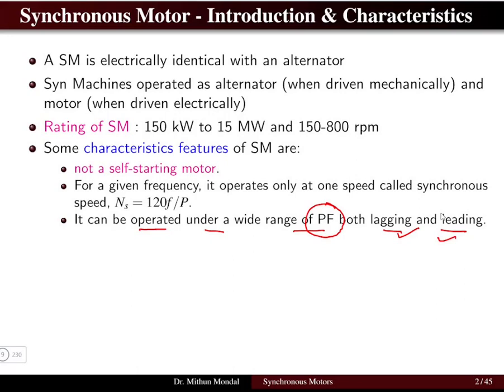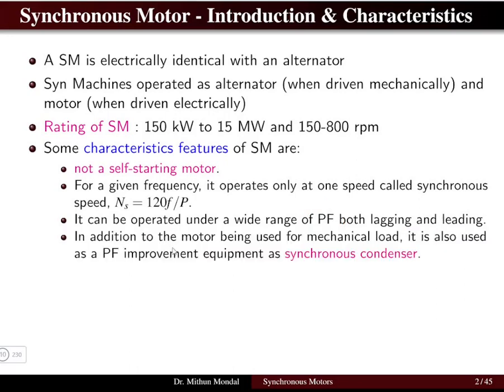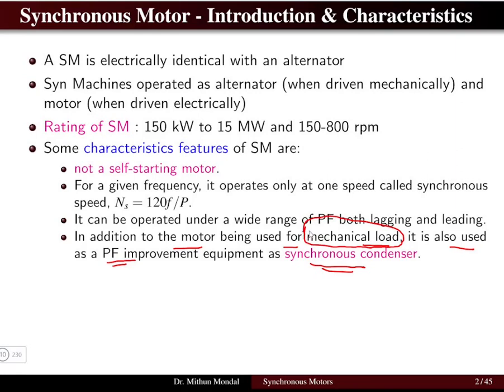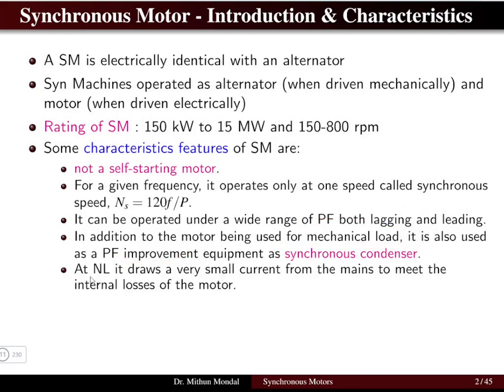Whenever we require a lagging or leading power factor we can make use of the synchronous motor. In addition to being used for mechanical load, it is also used as a power factor improvement device which is known as the synchronous condenser. So apart from using it as a mechanical load, since the synchronous motor operates for both lagging and leading power factor, it is used as a power factor improvement equipment.